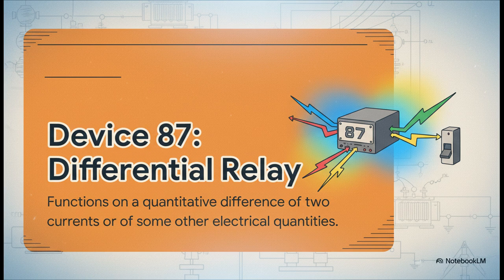What it does is it measures all the current going into the transformer and all the current coming out of it. In a healthy system, those two numbers should be basically identical, right? What goes in must come out. But if they're different, that means current is leaking somewhere inside the transformer itself, which is a very, very bad thing. It's an incredibly sensitive and fast way to detect an internal fault.